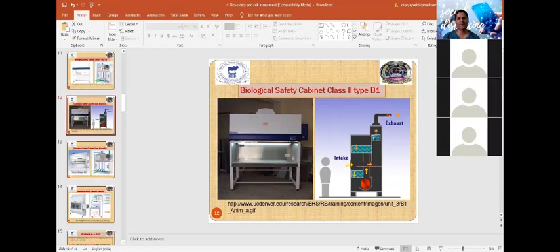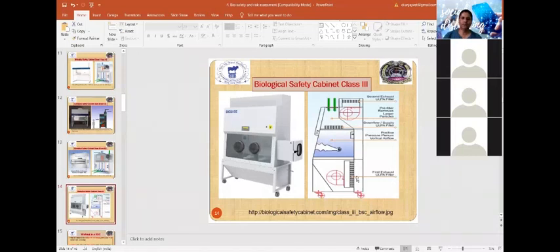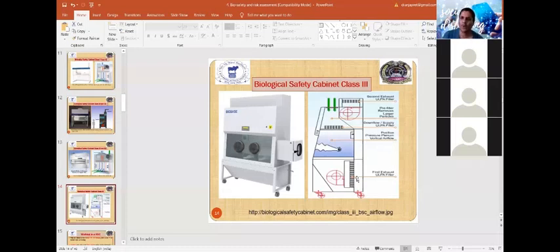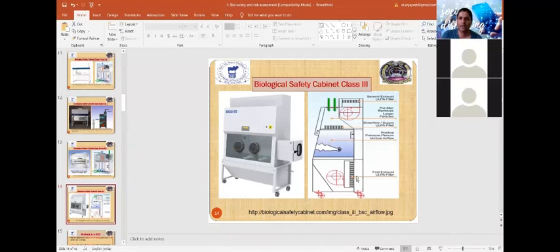For Type B1, similar airflow patterns apply with two HEPA filters. Type B2 may be fitted with a HEPA or ULPA filter. A major benefit of the Class 3 biosafety cabinet is that there is no direct contact between the persons involved in the procedures and the product. The safety of persons, the product being handled, and the environment are all protected.